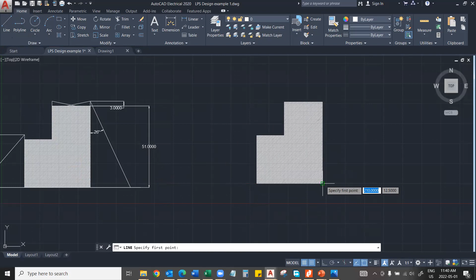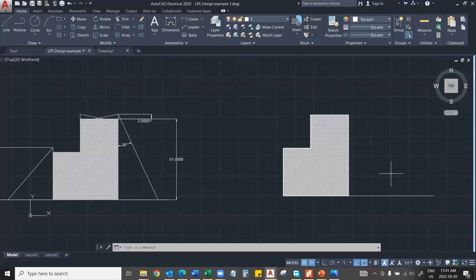So we are thinking of a particular case. With the current practice, you have to first identify the height of the building. Now it's 51 meters. If it's class 4, it will be fine. But even if it's class 3, you cannot handle it, because this is not defined beyond 45 meters. If class 4 is fine, but if it's class 3, then you cannot evaluate it with the protection angle starting off from this edge. You might have to consider somewhere over here instead, if it's beyond that.